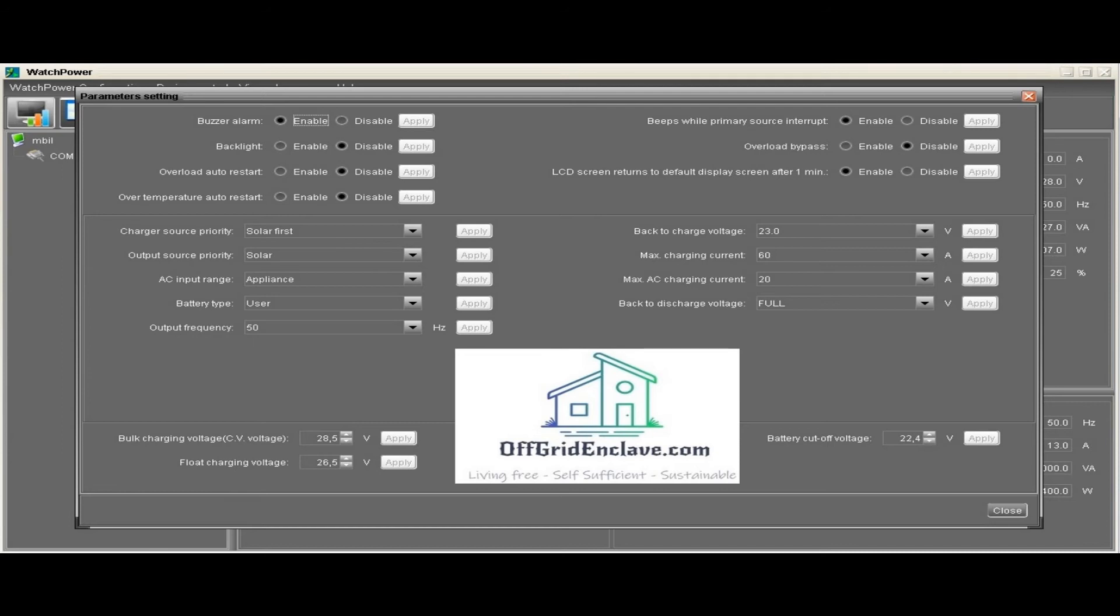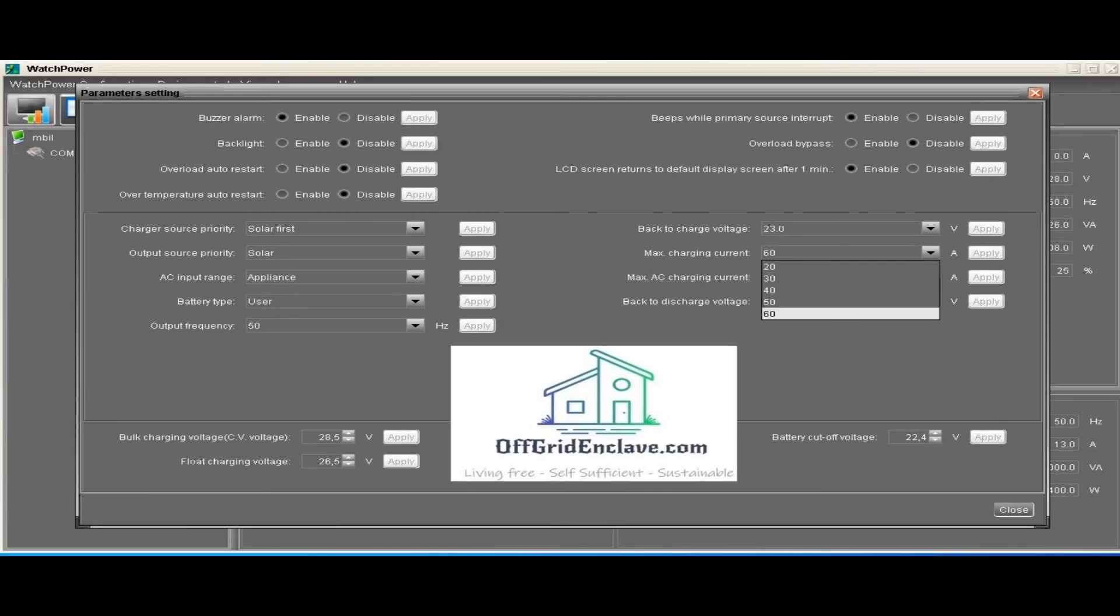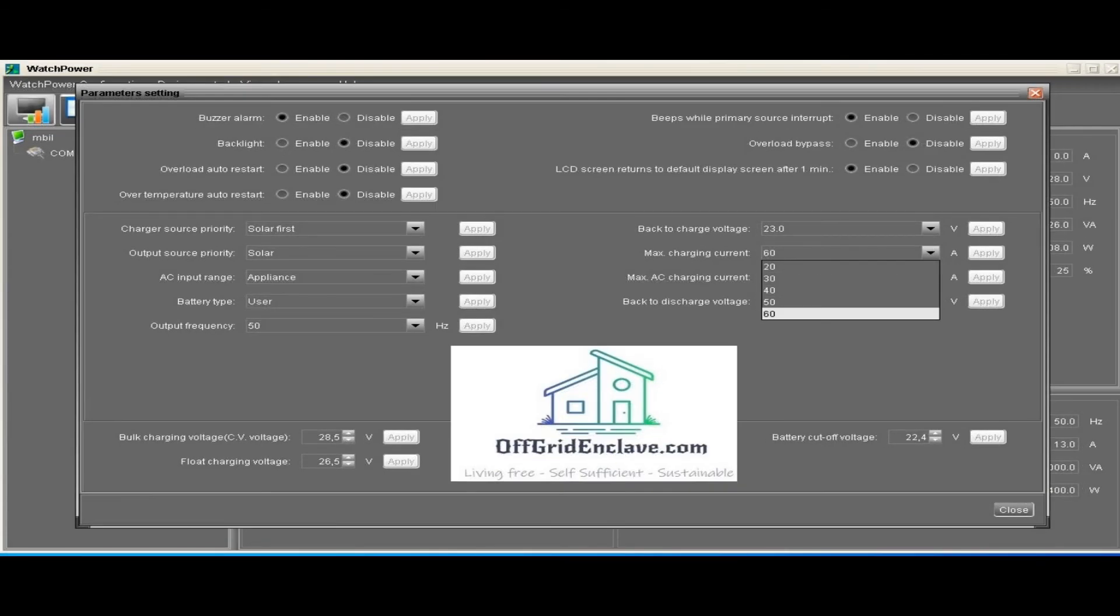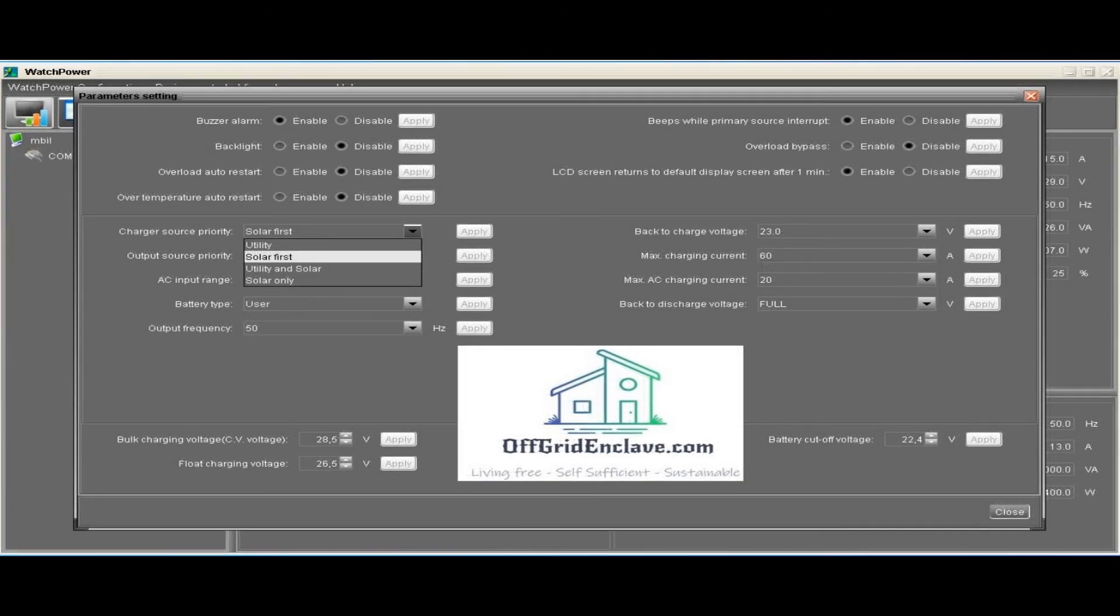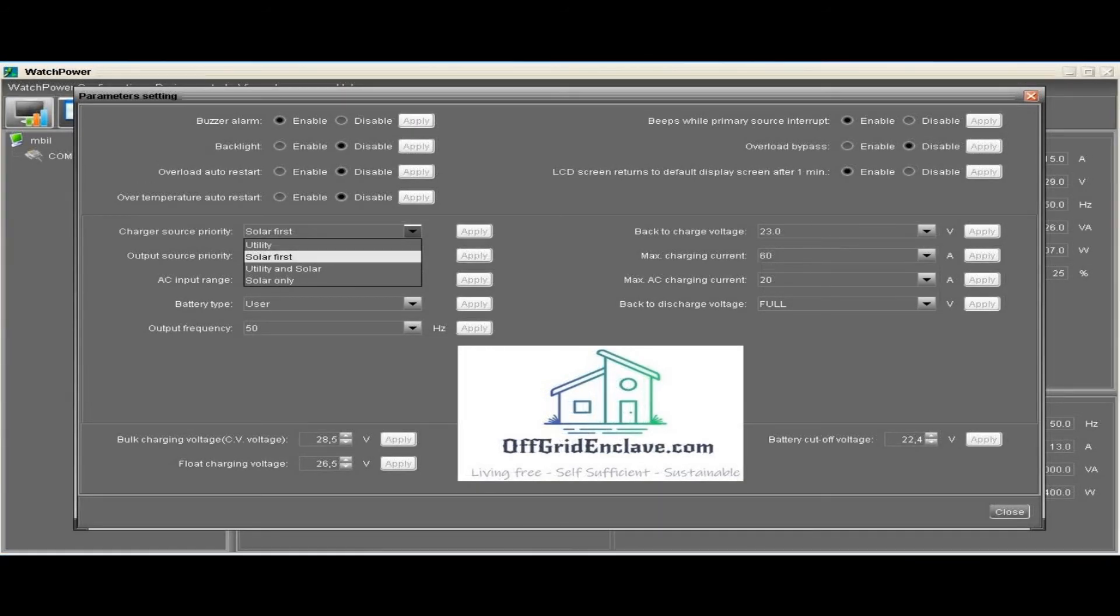Aside from standard settings like the battery voltages and the frequency for the inverter, there are a few settings at which we will have a closer look. Just like with the charge controllers you have the ability to limit the charging current for the inverter as well. For these off-grid inverters you can also configure the charge source priority as well as an option to select the output source priority.